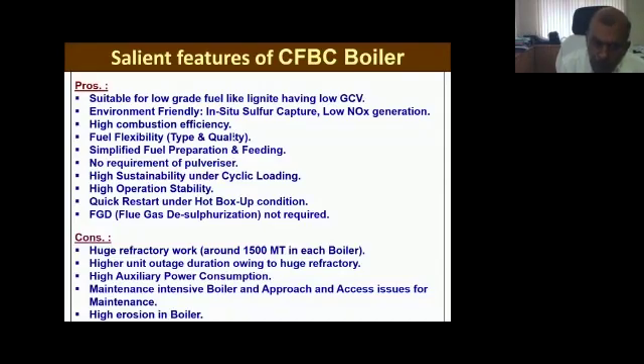In fuel preparation, it is simple. Why are we saying simple? Because all the participants are very much aware that in conventional power plants we use coal with grinders and mills, coal mills as we call them, and the output is 75 micron. Here, the lignite fuel size is minus 10 mm, so there are no pulverizers. We have 3 stages of crushing for the fuel. Since we have our own captive mines, the size is 1000 mm, then we bring it to 250 mm, from 250 mm to 50 mm, and then from 50 mm to 10 mm. This 10 mm and below particle size is directly fed to the combustor through the lignite feeder and other feeding arrangements.